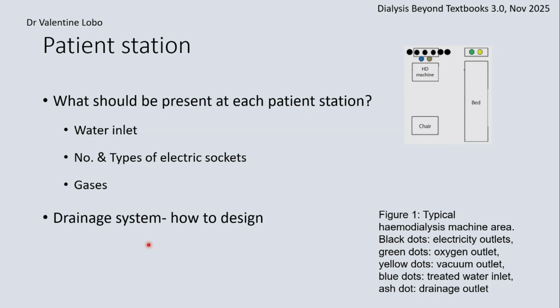Hospital safety guidelines say that your electrical lines and your oxygen line should be a minimum of 2 feet away from each other. That's particularly important if these lines are going to be concealed in the wall. Diagrams should be available showing where the electrical lines and the medical gas lines are. We once had a situation in one of the ICUs where a workman came to put in a sterillium stand on the wall and drilled into the oxygen line, because he just didn't know that it was concealed in the wall behind. So diagrams should be available showing where the concealed medical gas lines, electrical lines, etc. are.